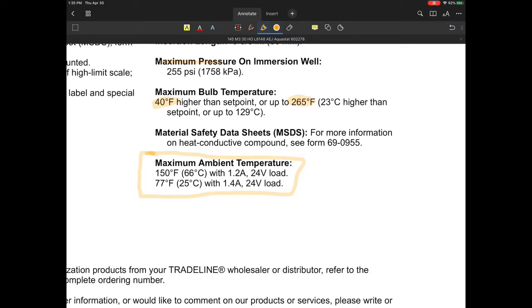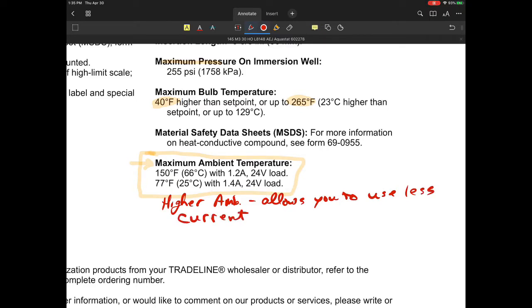This maximum ambient temp. The only thing I could think of is if you're in a boiler room or a mechanical room. They're identifying a maximum ambient temperature of 150 degrees with a 1.2 amp load on the 24 volt side, or 77 degrees with a 1.4 amp load. What they're really telling you is that the higher the amps, and this is true of wire, of relays, of almost all components, the higher the ambient, the less available current you can use.